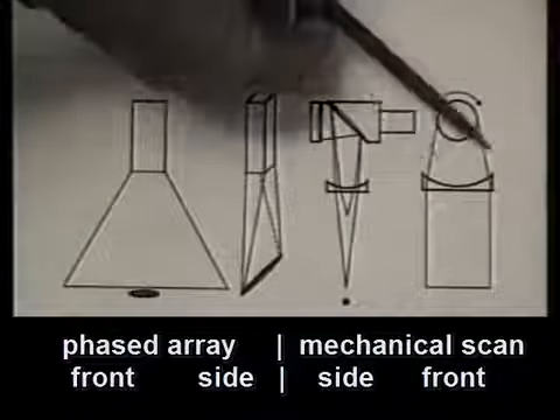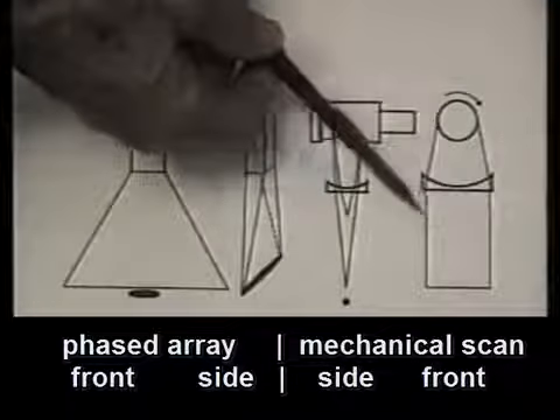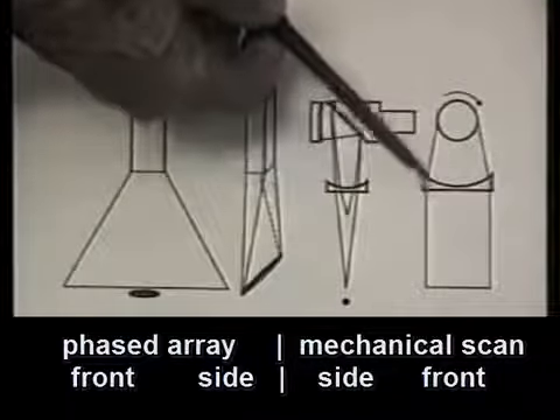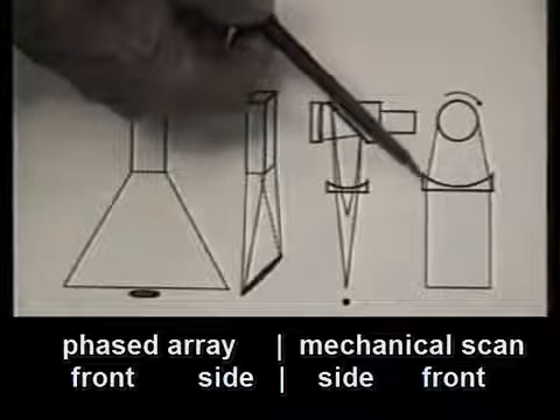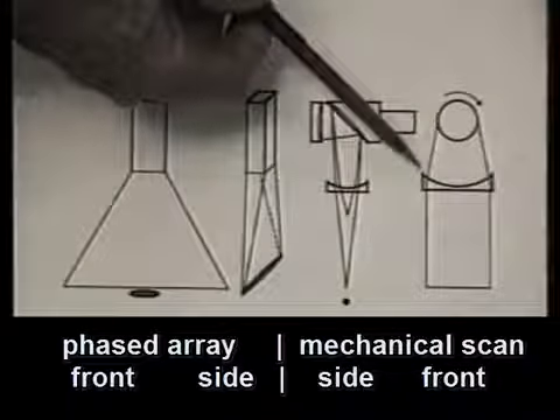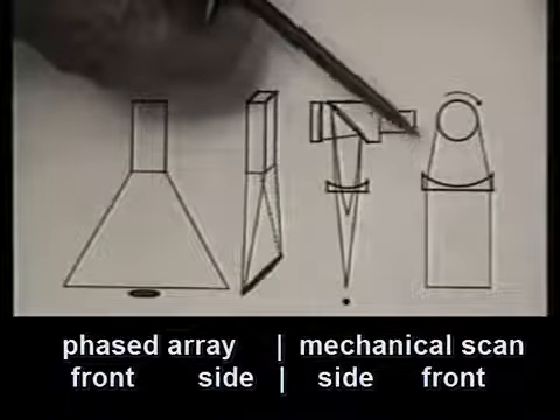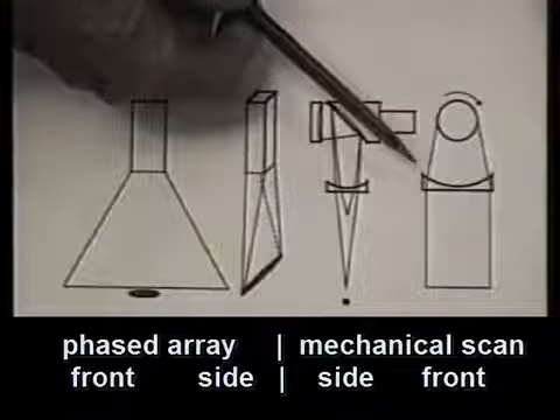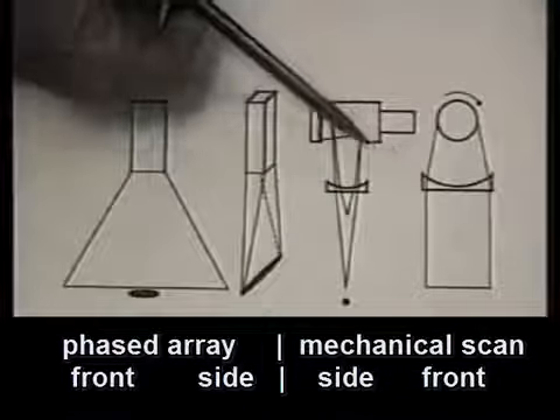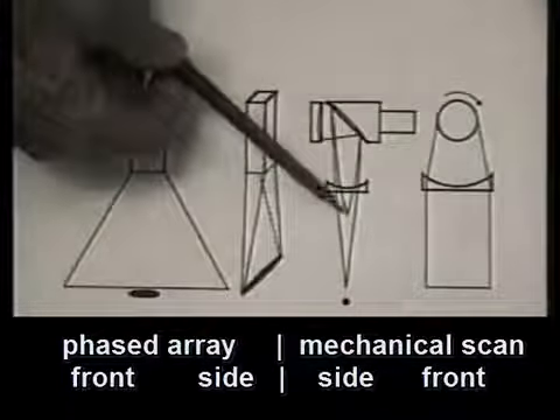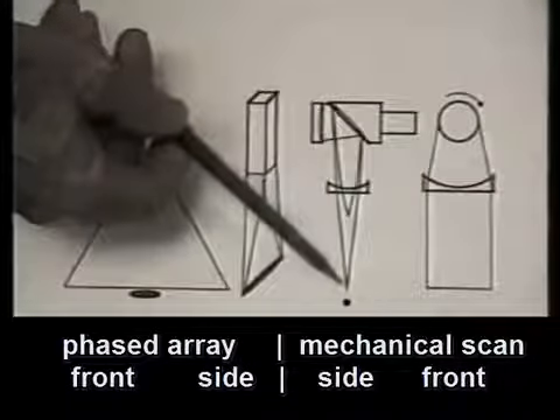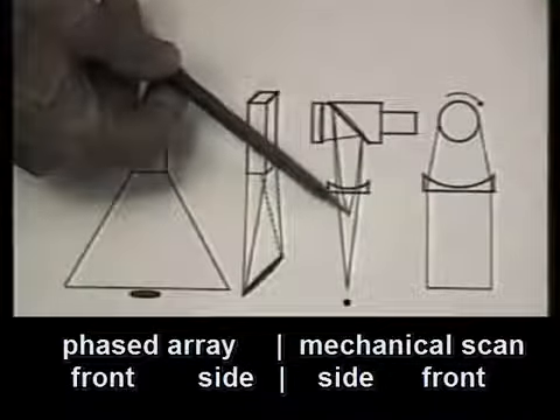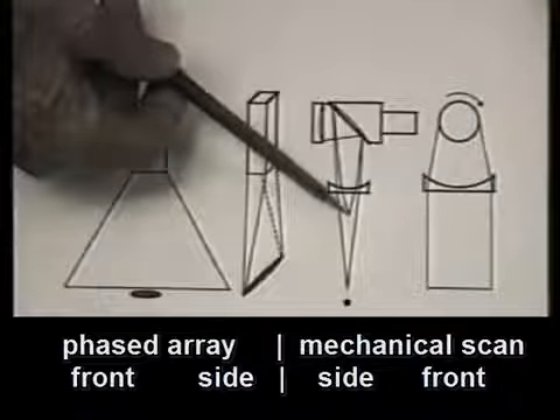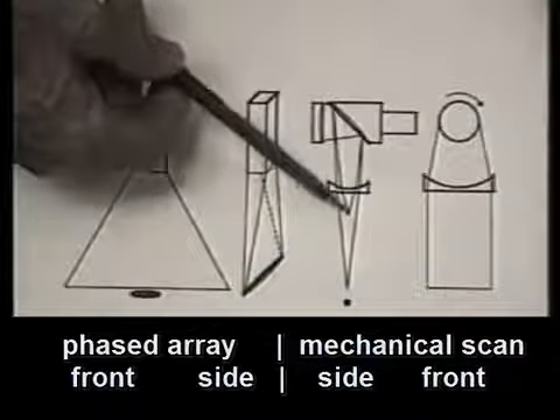The mechanical scanner also produces a pie-shaped scan, but the scan is converted into a rectilinear shape by a lens at the skin's surface. No electronic processing is required to convert the reflected image on a computer, and the transmit and receive beams are in focus within the same fixed range. This greatly improves the resolution and sensitivity at that range.